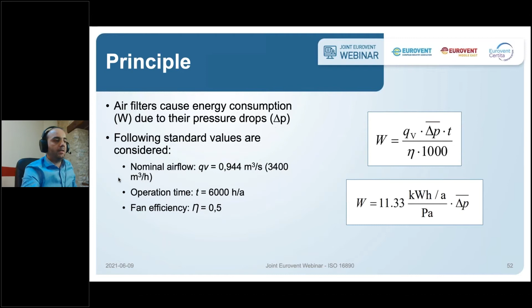And the energy consumption, W, can be computed by assuming some basic values. Here you can see the standard airflow used is 3,400 cubic meters per hour, an average operation time, which is assumed to be 6,000 hours per year, and an average fan efficiency, which is 0.5. From these assumptions, we can compute an energy consumption based on the average pressure drop of an air filter. And the formula below shows the numerical application. The energy consumption in kilowatt hours per annum is derived from the pressure drop in pascals. Next slide, please.